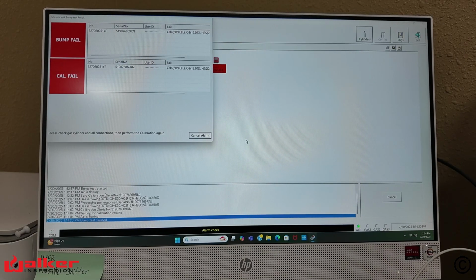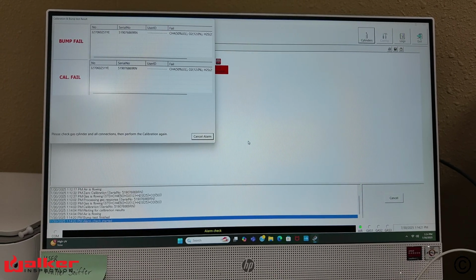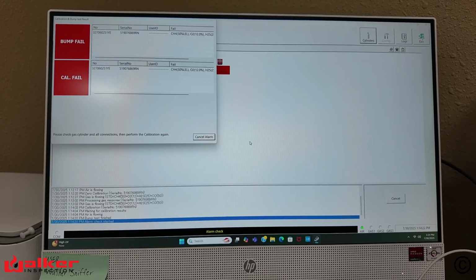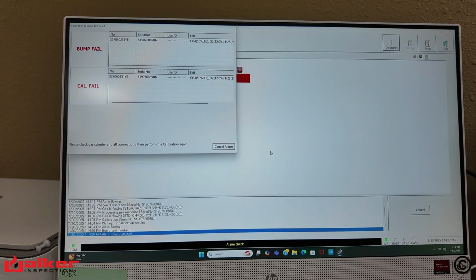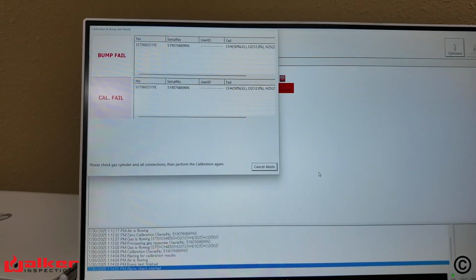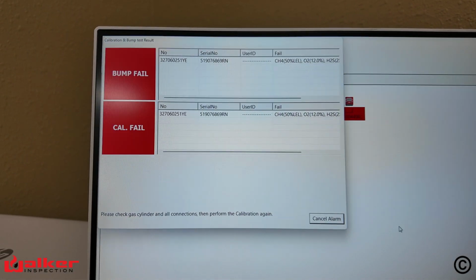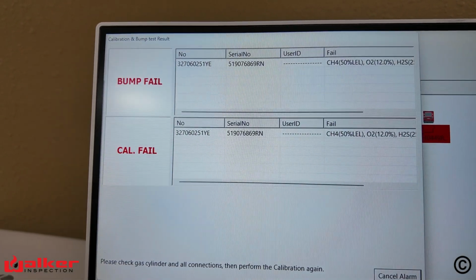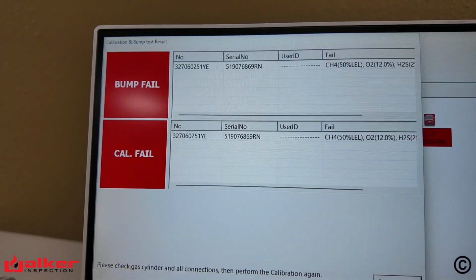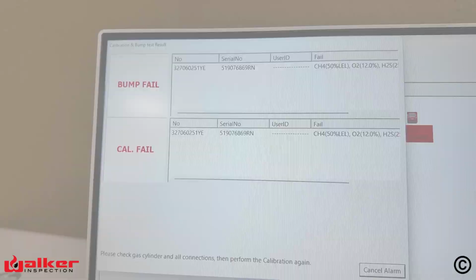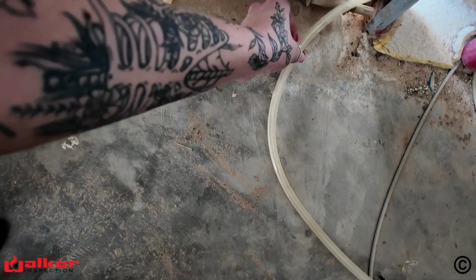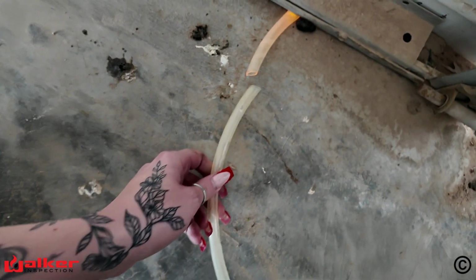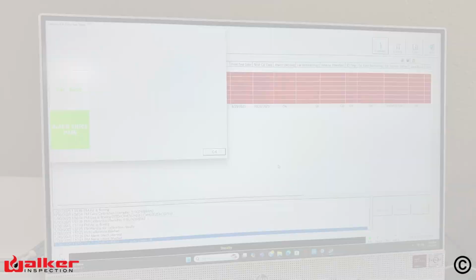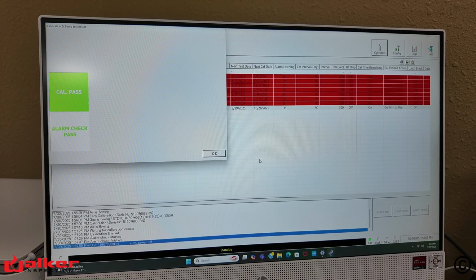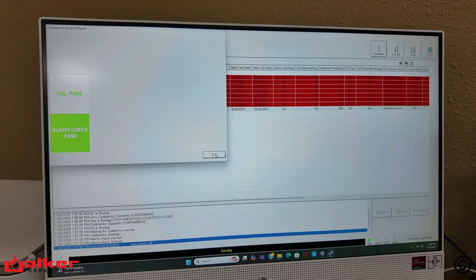If it blinks red, calibration fail, this means that the hoses, connections, and troubleshooting process needs to be gone through. If none of the troubleshooting processes work, please contact your area manager as there may be a problem with the monitor. Here is an example of a failed test. This one failed for 2 reasons. The hose wasn't connected to the right nozzle on the docking station, and the hose was pinched off by an overhead door outside. Once calibration is complete, it should show a green blinking icon saying Calibration Pass.